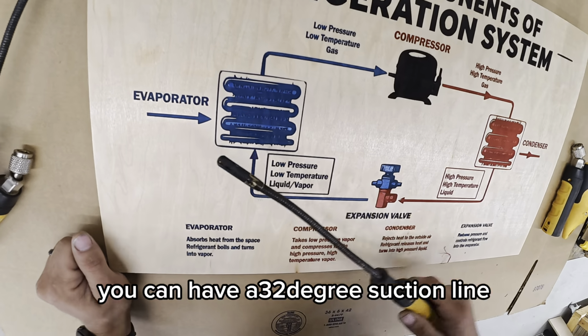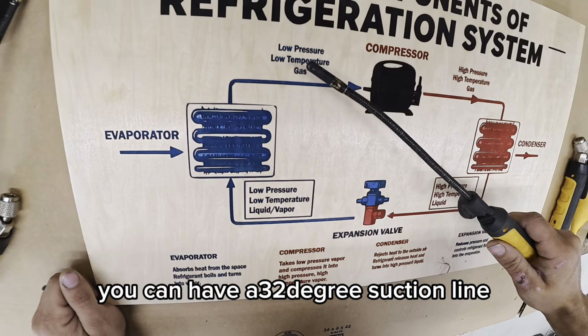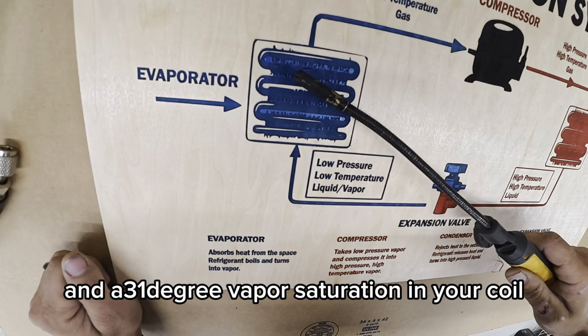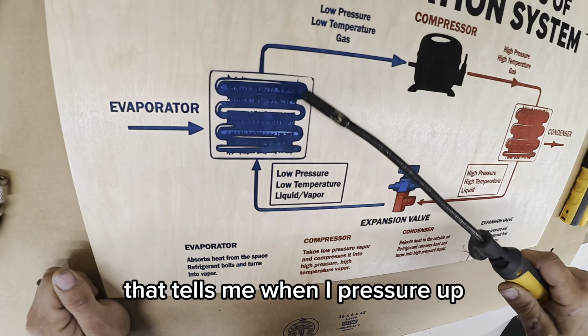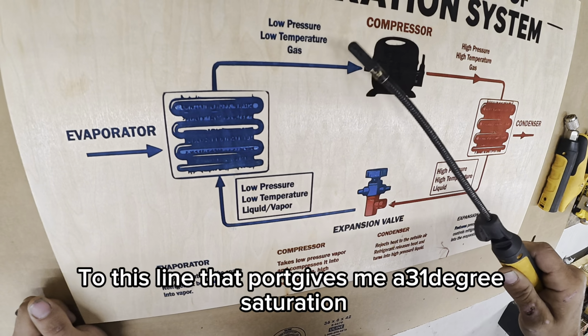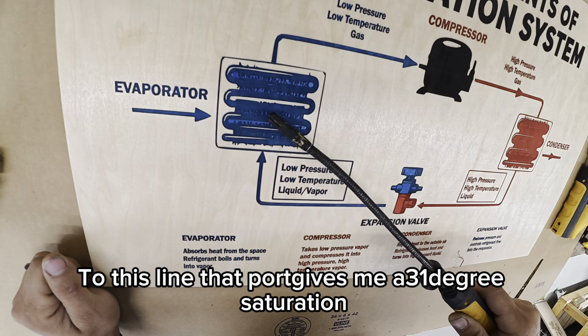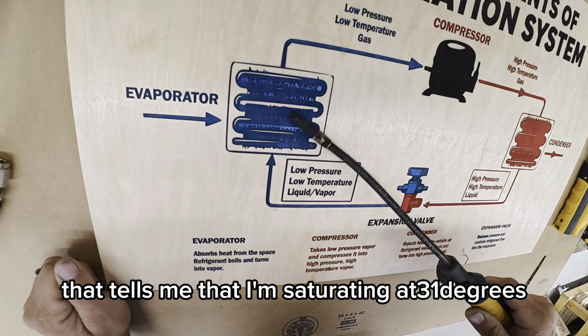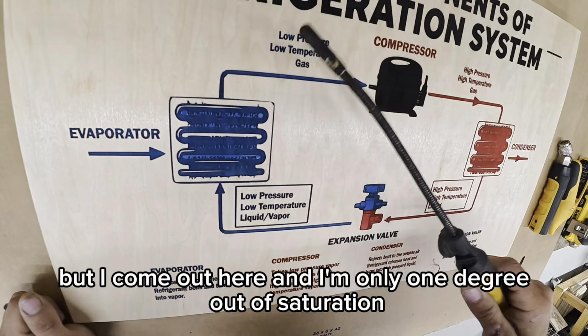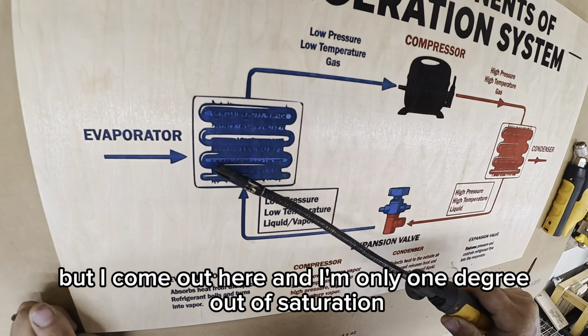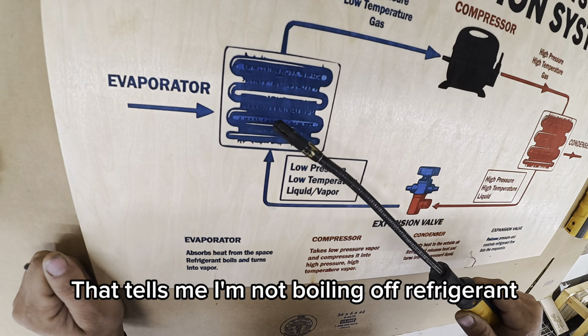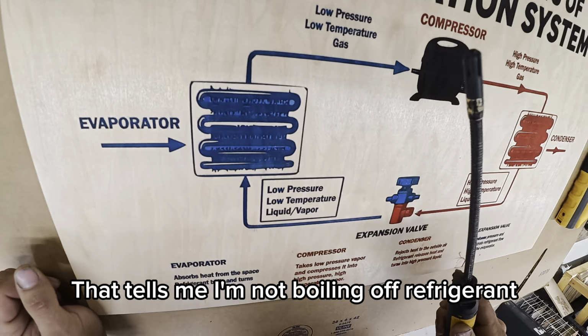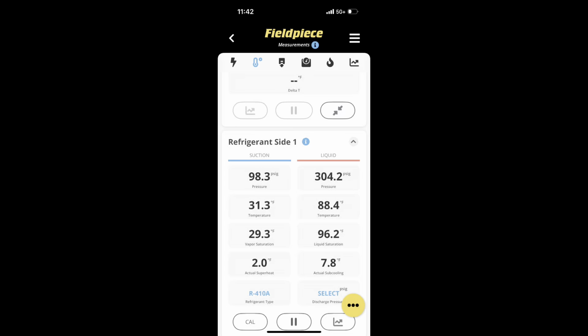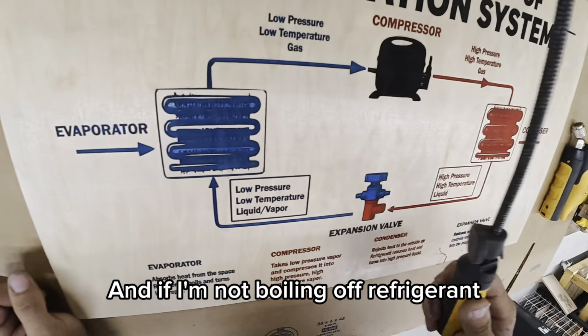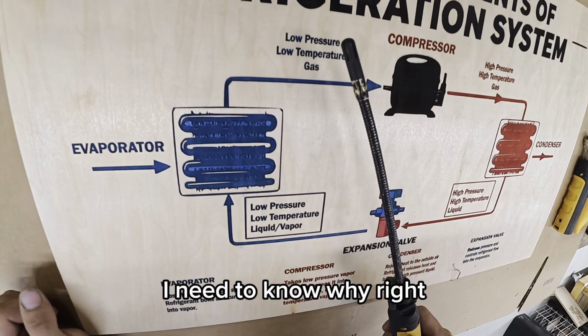So in some cases, you can have a 32 degree suction line and a 31 degree vapor saturation in your coil. That tells me when I pressure up to this line, that port gives me a 31 degree saturation. That tells me that I'm saturating at 31 degrees, but I come out here and I'm only 1 degree out of saturation. That tells me I'm not boiling off refrigerant. And if I'm not boiling off refrigerant, I need to know why, right?